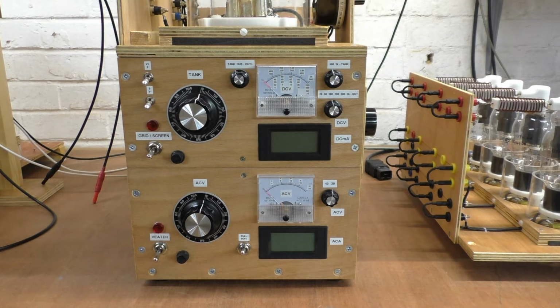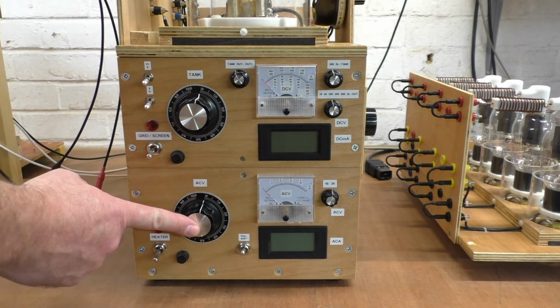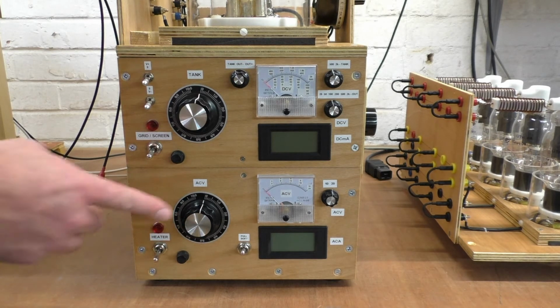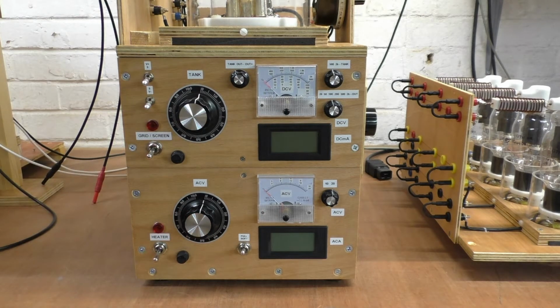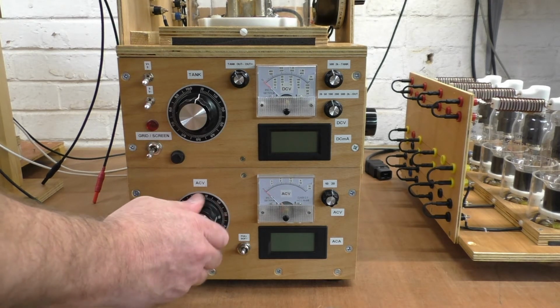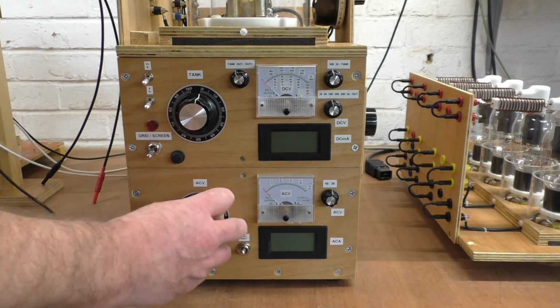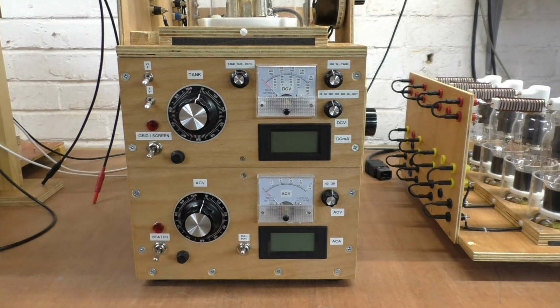And obviously different tube boards have different requirements. Plus also we may want to only use one of the tubes or configure the tubes to run differently with each other, and therefore we might want to adjust some of those parameters. So we need a very flexible heater control, and we accomplish this by using a variac. So this is a nominally 1 amp variac. Obviously this is UK line supply at 240 volts, and by adjusting this we can adjust the output of the toroidal transformer, which is then connected to the heater circuits.